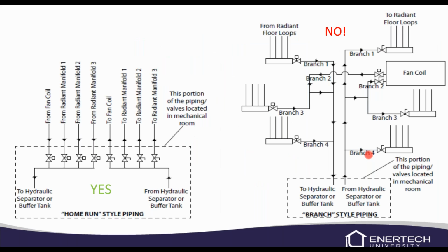We do recommend the home run style piping. Basically what that means is all your valves and your header are in the mechanical room. It makes it easier for flushing. You can go to the valve and open it or close it without climbing into the attic or going down the crawl space or going to wherever that zone is at and opening that valve.